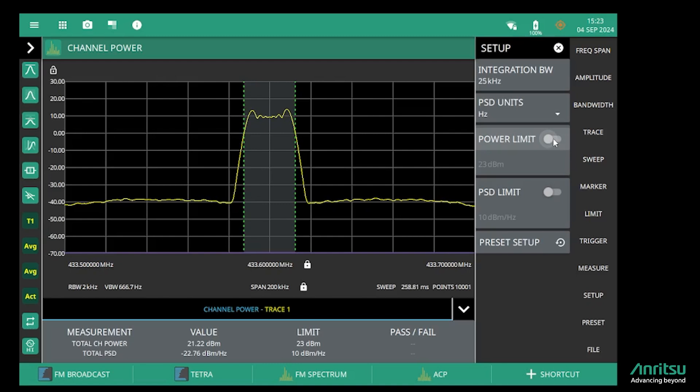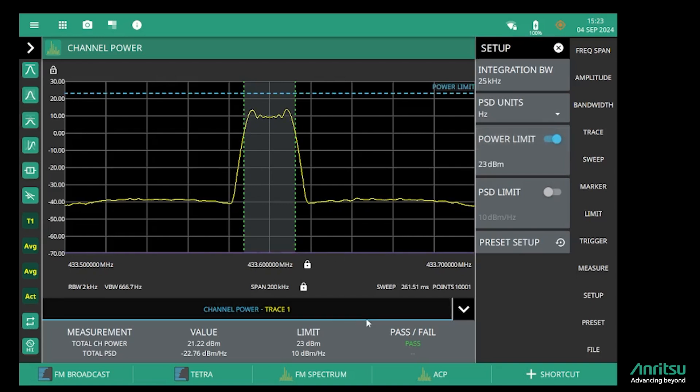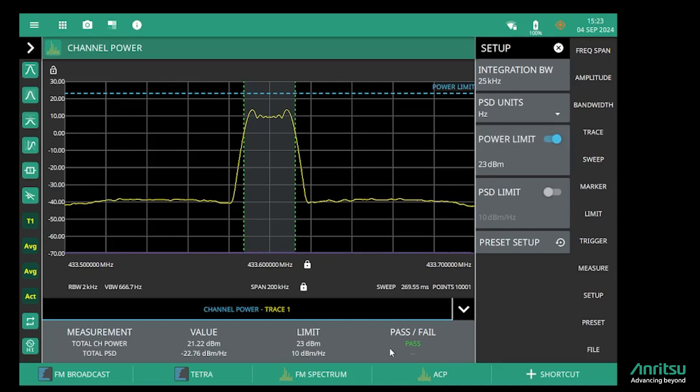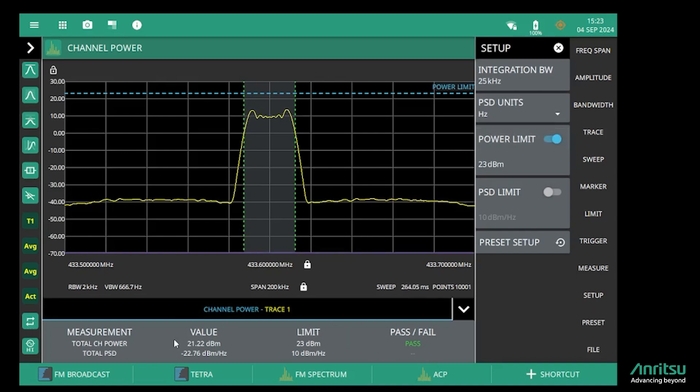I can also apply a limit to that, so if I have a direct connection to the transmitter and there's a maximum power that the transmitter can transmit, I can set that and get a pass-fail result. The instrument also shows me the power spectral density in dBm per hertz.